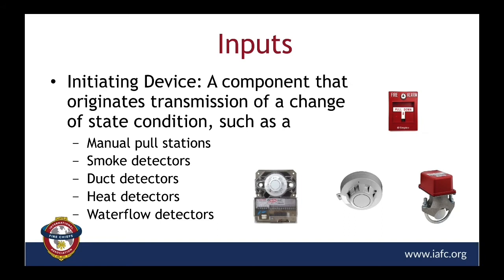And the detecting element within the heat detector will activate when it reaches a predetermined fixed temperature, or when a specified rate of temperature rise occurs. So if it's a slow moving temperature rise, the fixed temperature will take care of it. But if it's rising very quickly, it may activate before the predetermined set point. Now, water flow detectors or switches, they detect movement of water from an activated sprinkler head by a paddle device that's inside the sprinkler pipe. So obviously, if there is an alarm condition, the sprinkler head goes off, you want to be able to detect that water flow, send a signal to the control unit, which then notifies the fire department.